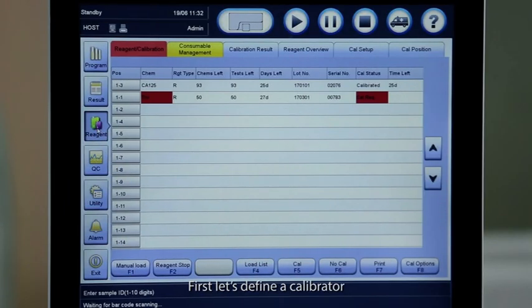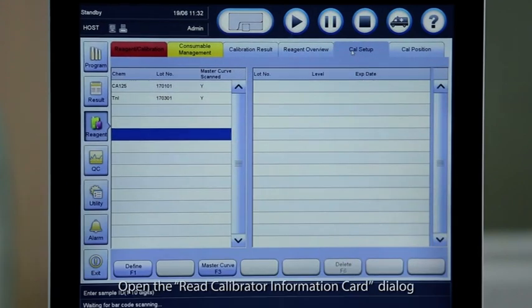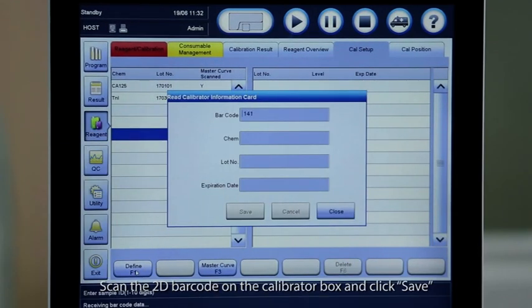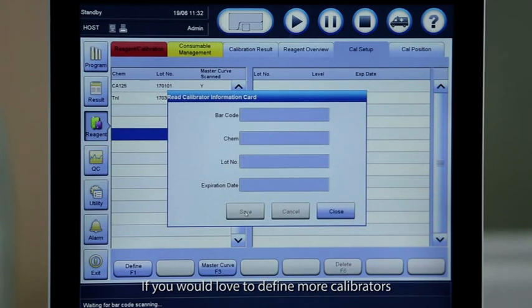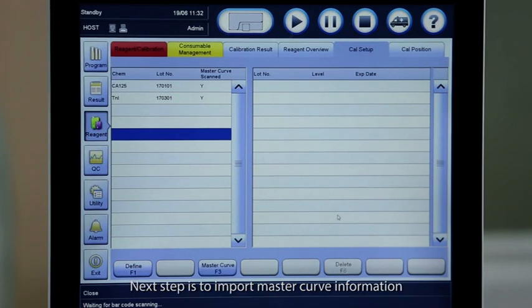First, let's define a calibrator. Open the read calibrator information card dialog. Scan the 2D barcode on the calibrator box and click save. If you would like to define more calibrators, scan more barcodes on the calibrator box.